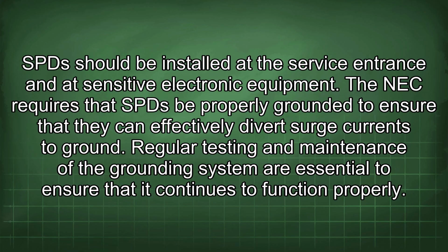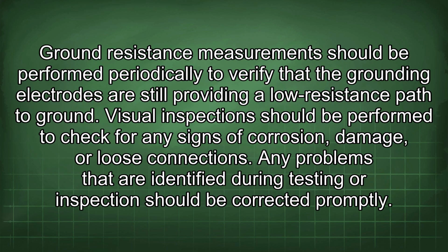Regular testing and maintenance of the grounding system are essential to ensure that it continues to function properly. Ground resistance measurements should be performed periodically to verify that the grounding electrodes are still providing a low resistance path to ground. Visual inspections should be performed to check for any signs of corrosion, damage, or loose connections. Any problems that are identified during testing or inspection should be corrected promptly.